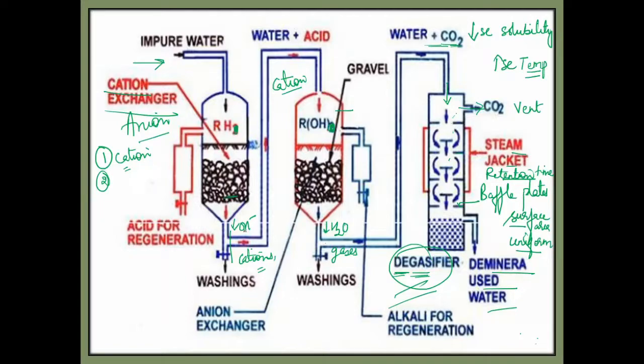And calcium reacts with hydroxide and it forms calcium hydroxide. So when this comes here, the water is comparatively basic and it is going to create trouble further. Either it is going to corrode, so corrosion is a big problem, or it is going to precipitate out, like magnesium hydroxide and all. And above all, your hardness is at risk because you have not yet removed the hardness.